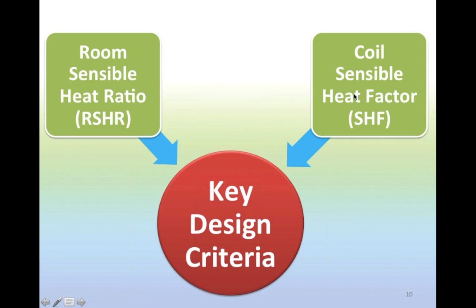Then when it comes to the cooling coil, as I showed you in the earlier schematic, we take in a certain amount of ventilation air. So you have to add the system requirements in terms of the ventilation energy requirement, and you get a slightly different number in terms of the coil sensible heat factor. So you have two things. One is at the room level, the room sensible heat ratio. It has a certain ratio in terms of sensible and latent load, and then you have a coil that needs to handle or offset these loads.